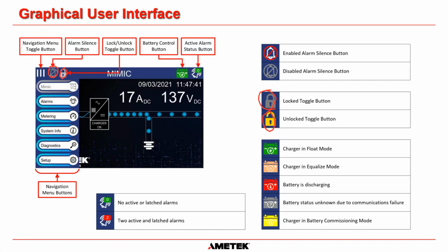You can also log back out if you're logged in by clicking on the gold unlocked button. The next thing we have in the middle of the screen is just the title of the screen. We call this screen our mimic screen. Then we have our battery control button. When the battery is green, like it is here, the system is currently in float mode. By clicking that, you can change it to equalize mode, which is this amber button here. When the battery is discharging, like it was in that last video we saw, you can't click on the button and change anything, but it'll at least show you that the battery is discharging with this red battery button.